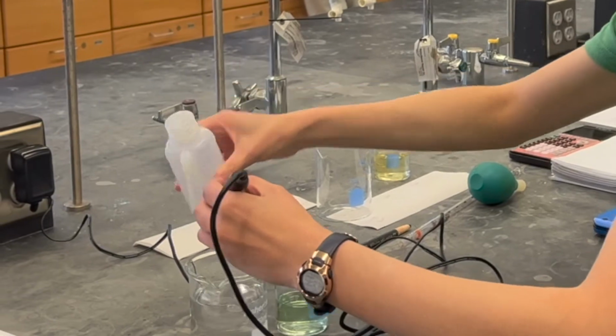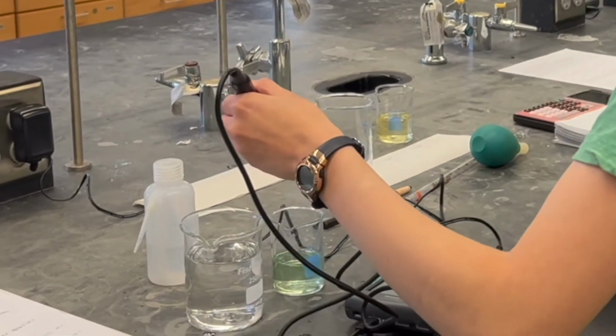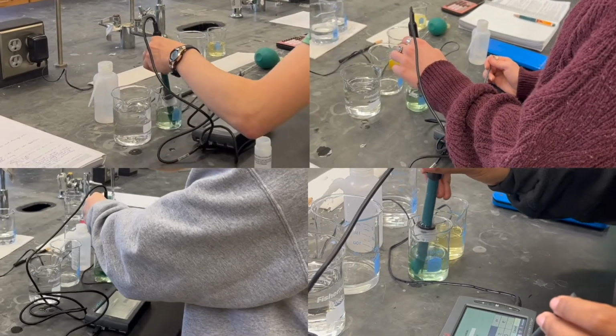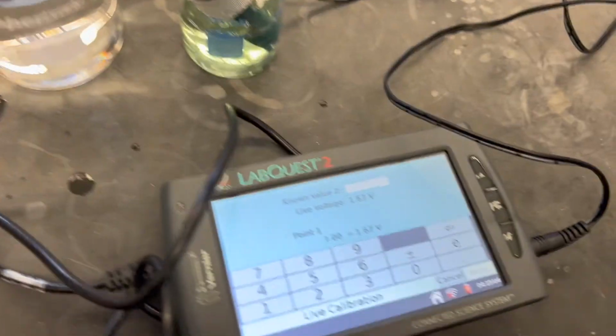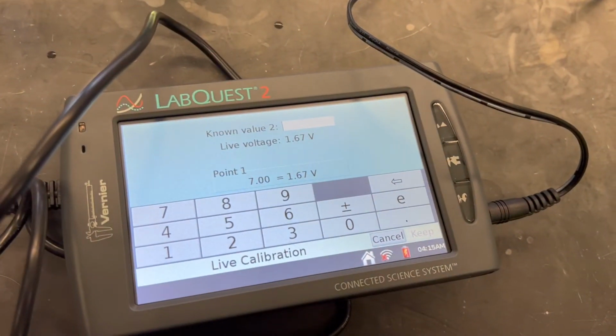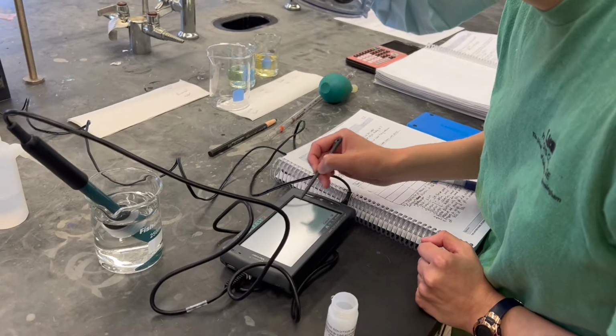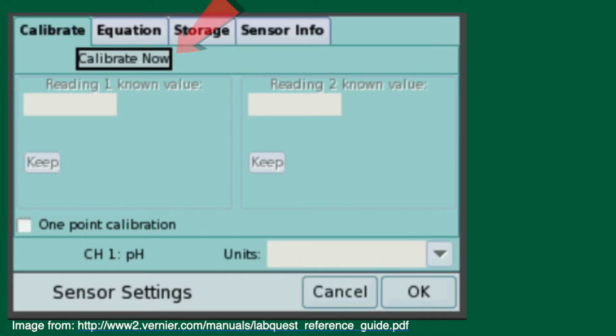The probe is first placed into a beaker of pH 7 buffer solution, and lab members swirl the probe gently in the solution until the value shown stabilizes. Then, using the stylus, group members enter the LabQuest program on the pH meter, navigate to the Calibrate Now function, enter a pH of 7 for the first buffer, and press Keep to save the value.